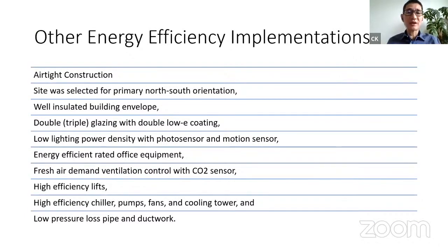The rest of the energy efficiency implementations are actually very standard, I think. We have a very airtight construction, which not only reduces energy but is required for the chilled beam, because if it's not airtight, the outside air is moist, and when it touches the chilled beam, it will start to condense in the occupant space. That's not what we want. So the building was designed especially airtight, so we get a lot of exhaust air for the heat recovery, increasing our efficiency further.